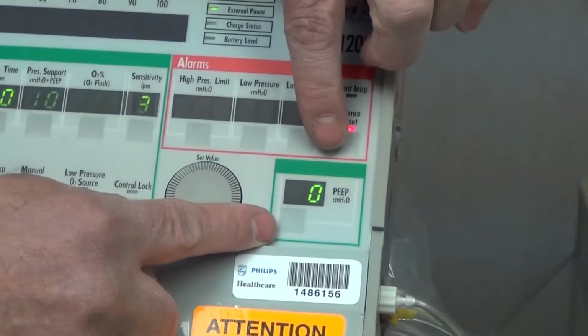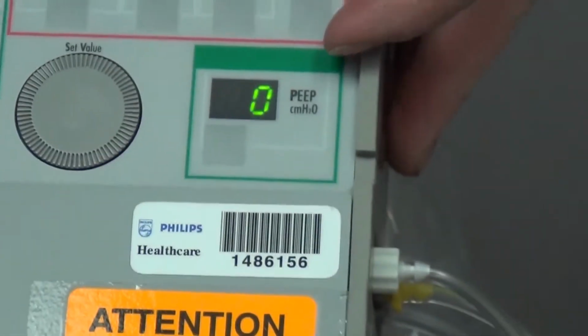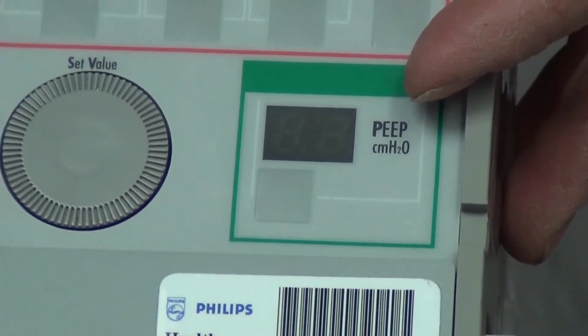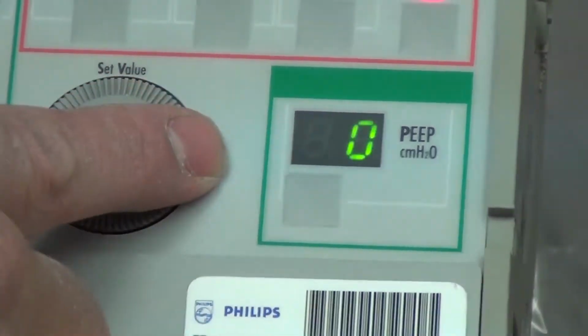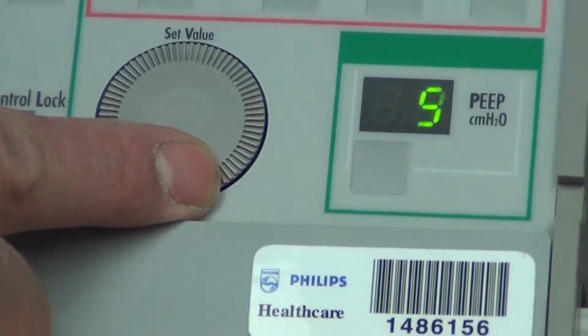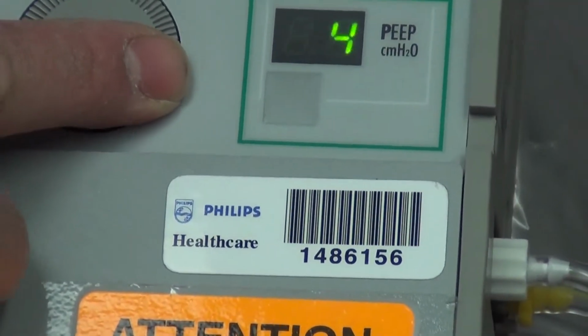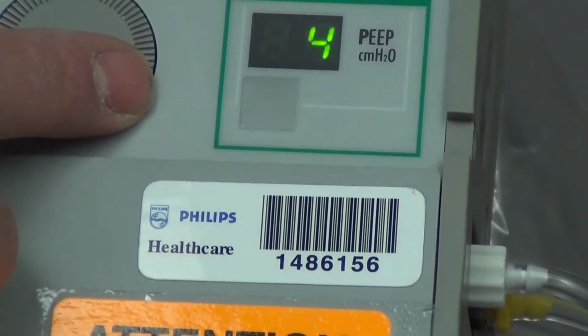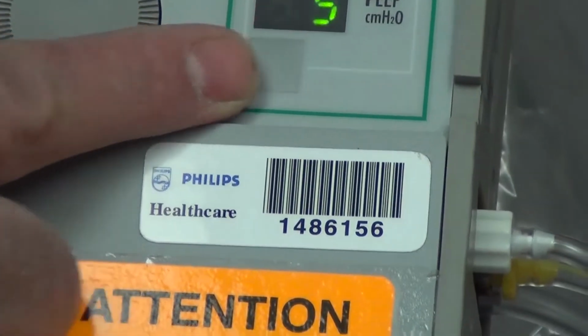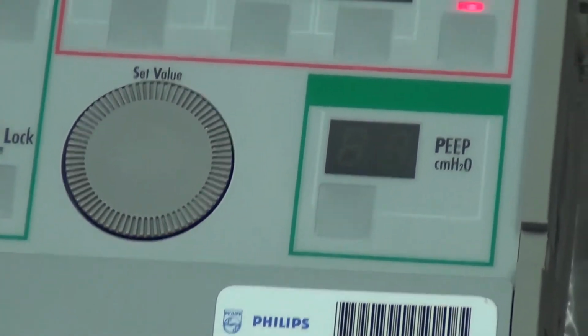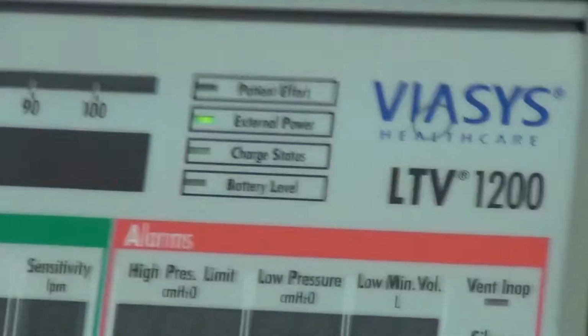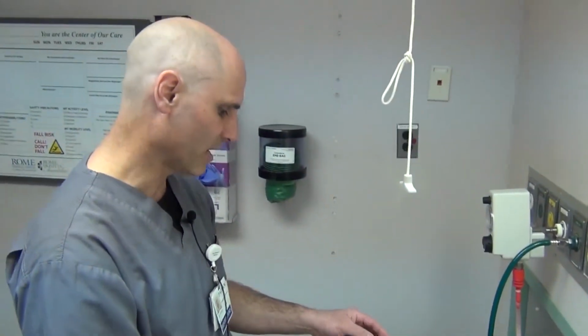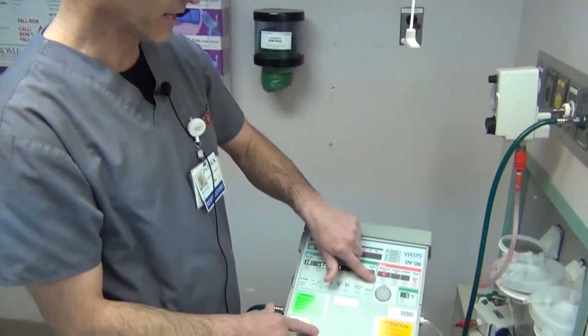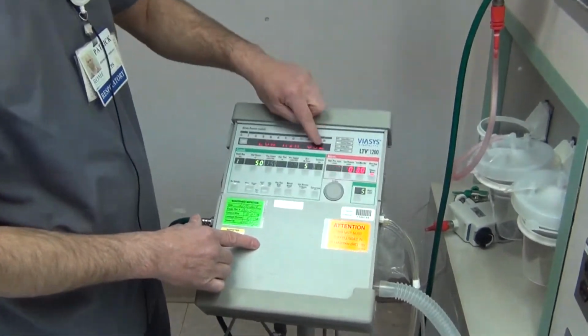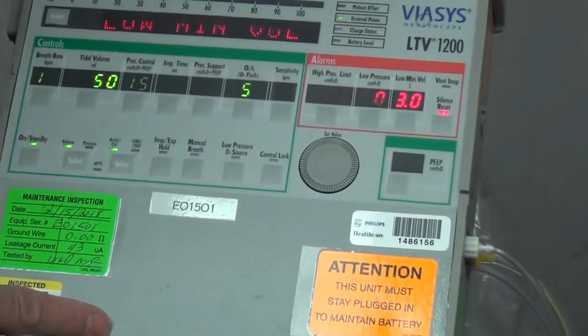And then we're going to go down to this little green box right over here. This little green box here is your PEEP. We're going to put that, and this is again a setting that the physician will prescribe. A lot of times we usually use 3 or 5. We'll hit accept. And now we would get to the alarm portion or the safety portion of the device. And if you look, everything that you set initially is in the green box. Then after that, it's in the red box.